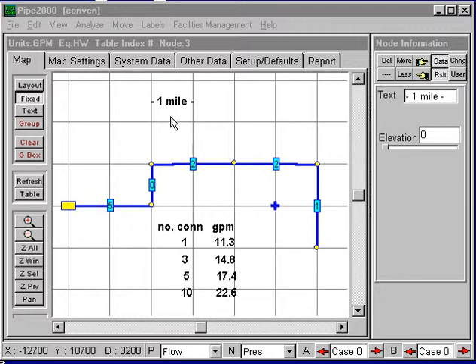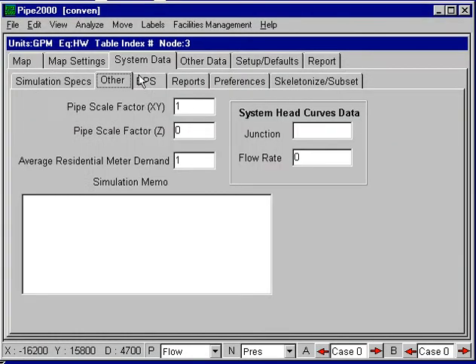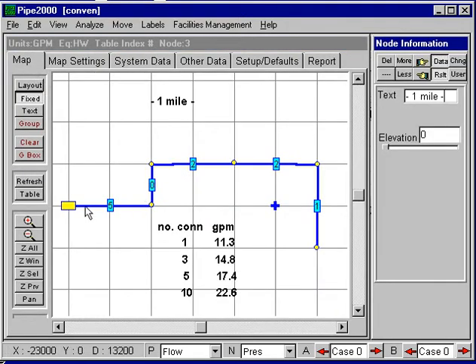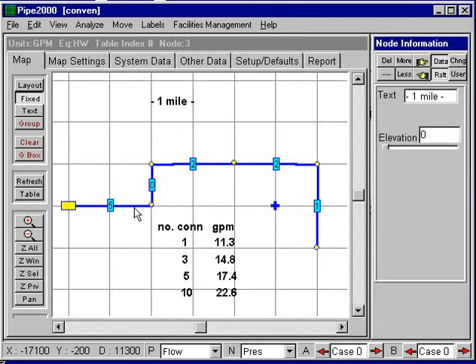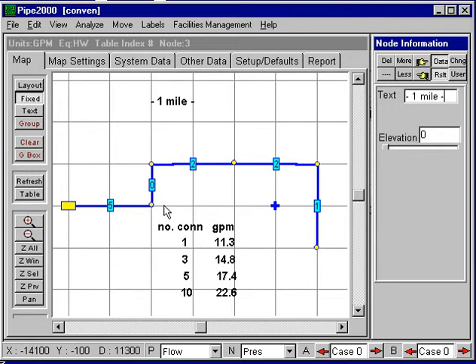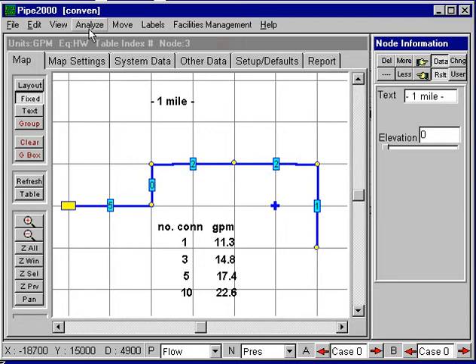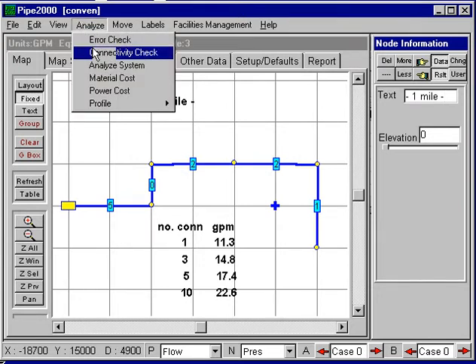Within the database, under the system data, we have an average residential demand of one gallon per minute per meter. When we do a conventional analysis, we basically distribute the demand to either end of the line, or if it has a fixed grade node, we put the demand at the far end. So this line would have a five gallon per minute demand, this line would have one at each end, and this would have 0.5.